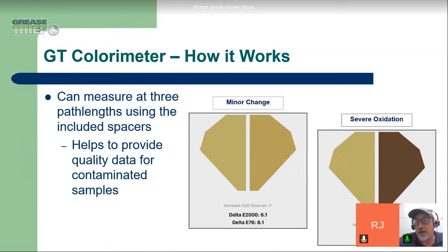And he said, oh, you'll have problems on number 3, number 4, and number 8. I was like, well, how do you know that? Were you doing other testing when I was pulling the grease samples? He said, no, I can just tell by looking at the grease sometimes. So he kind of gave us that idea that there is something from a visual standpoint, or at least an observable, visible light difference in the grease that tells us that there's some issues there.